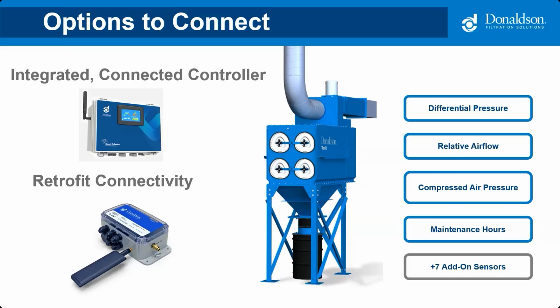for you to manage. On the right-hand side, I'm highlighting the basics of what IQ monitors. So number one, we're always tracking differential pressure across the filters. We want to know the filters are okay. But as I said before, differential pressure or filters plugging, especially prematurely, is a great indicator of something else going on as well. So it's great to track that first and foremost. It also tracks the relative airflow in your main duct. So you can monitor if you're getting the flow rate that you expect, which can be indicative if somebody's misadjusted that damper I talked about, or an airline has plugged and now your fan is blowing harder than it should because it's not getting a good reading.